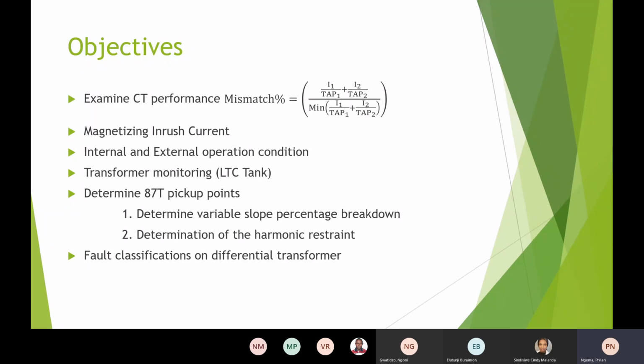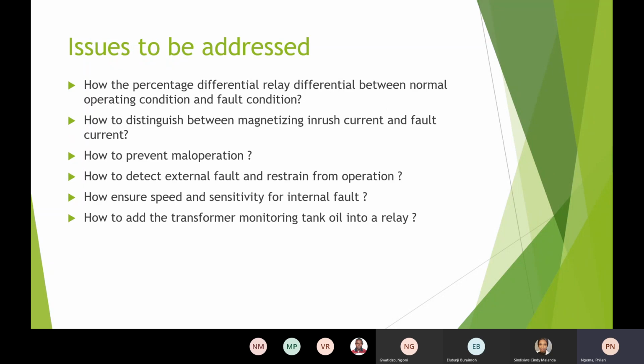Then also, going to the fault classification on a differential transformer, the question will be how to ensure that the relay sees the difference between the normal condition and the fault condition. That is one of the questions that needs to arise in this research: distinguishing between inrush and fault current.